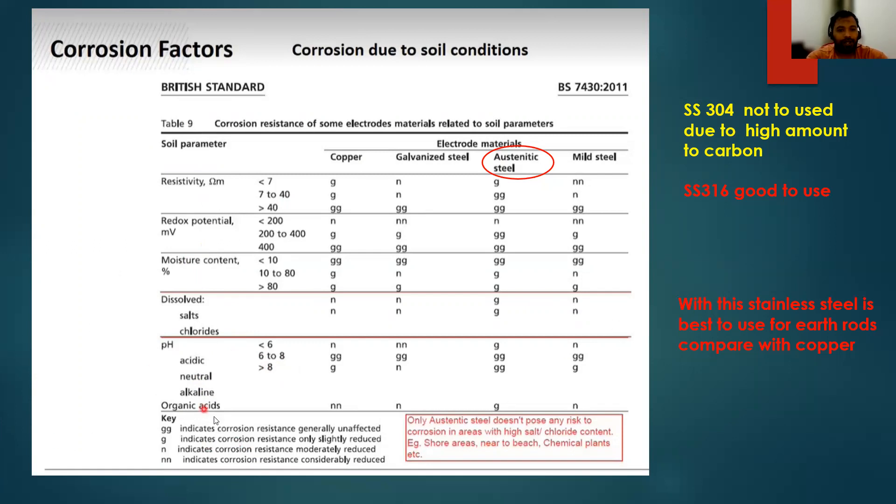If there are alkaline organic acids in the earth, what will happen? GG indicates corrosion resistance generally unaffected, and G indicates corrosion resistance only slightly reduced. N indicates corrosion resistance moderately reduced, and double N indicates resistance considerably reduced. If you've got G and GG more, then it is a good earth rod. If you see this pH condition, I am mostly comparing copper.